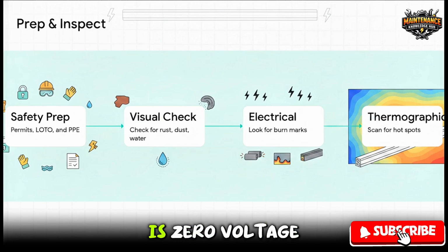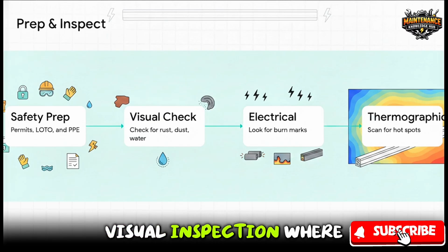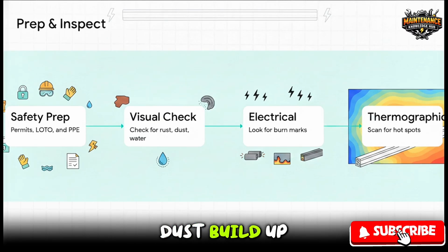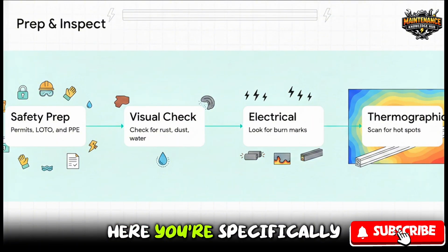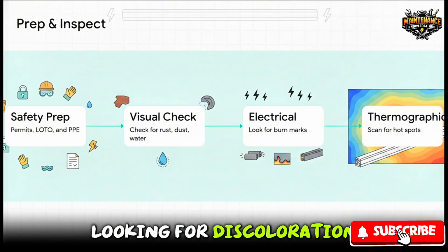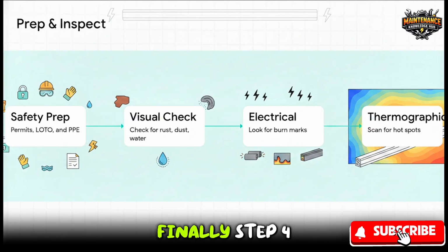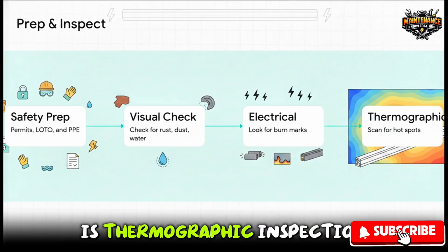You verify there is zero voltage and you get your arc-rated PPE on. Only then do you move to step 2, visual inspection, where you're hunting for rust, dust buildup, or any signs of water getting in. Next is the electrical inspection. Here you're specifically looking for discoloration, burn marks, or loose joints. Finally, step 4 is thermographic inspection.